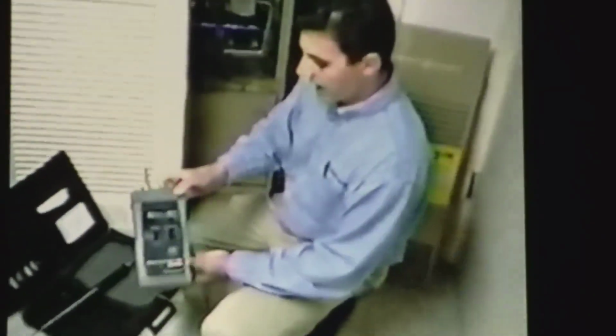And here we have great access because this is not a higher efficiency furnace with an exhaust fan. On this particular unit, we have the draft hood. So I can take my readings right up inside the heat exchanger area and inside the actual draft hood box. So, as you can see, we've got this calibrated at 0. And I'm going to place the probe in the draft hood area.